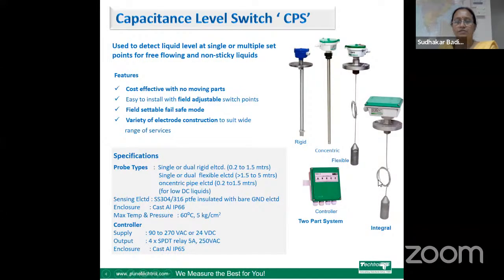Then capacitance level switch. This is again a site adjustable switch, which is used for single or multiple set point detection and which is used for free flowing and non-sticky liquids. As it has no moving parts, it needs little or no maintenance and is easy to install. Then a variety of electrode constructions are available to suit the site conditions. It is available for the range up to 5 meters.